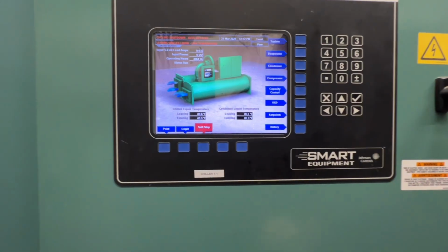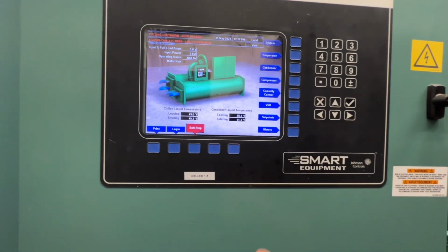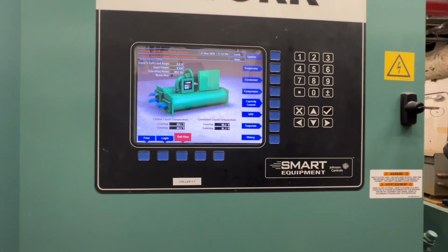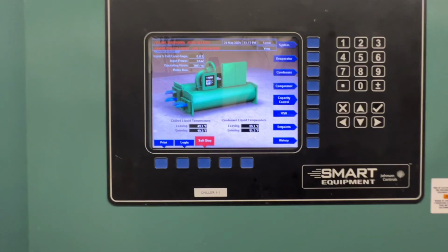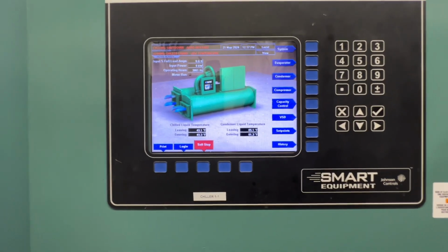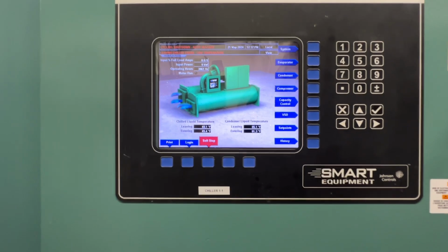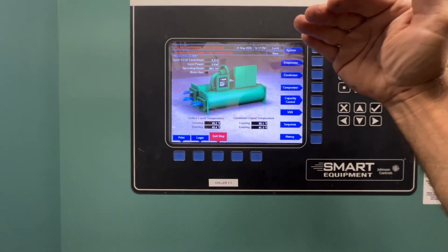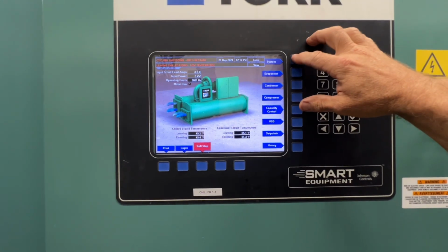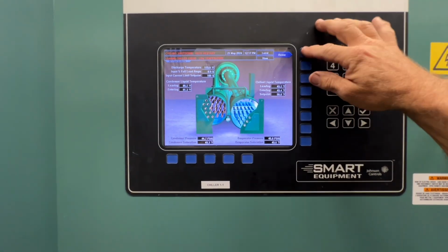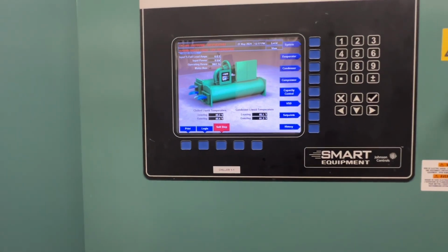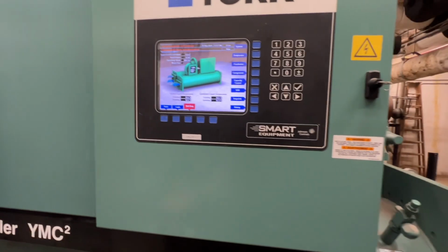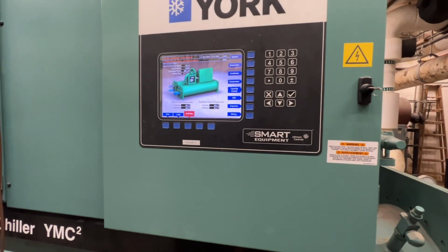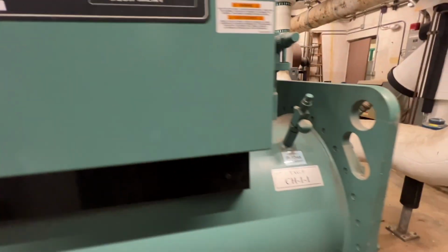So we backed it off, and that noise that you heard was actually the check valve on the compressor discharge, that pinging noise, because it was trying to back off on load and couldn't go any lower than like 35%, so it was just creating that surging, knocking noise. So yeah, he raised the leaving water temperature on this one to 50.